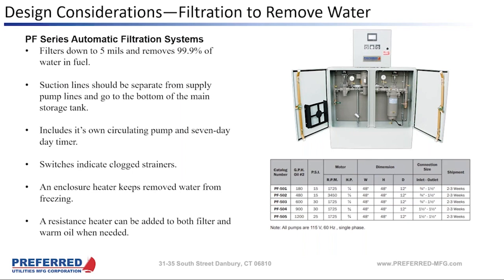But for most places, what I recommend is periodic filtering for water content, because that's something that's going to be coming in every thermal cycle down through your vents. But really, after a delivery is when you're going to want to take a look at it as well. So it really depends on your delivery cycle, the amount of fuel that you've stored, and also looking at what your shifts are. Is this something where you're going to want to start and stop it within a single person's shift, or are they going to hand this off to somebody else? Is third shift going to have to address an alarm on it? So those are the sort of things that we need to look at when determining how often something like this should be run.